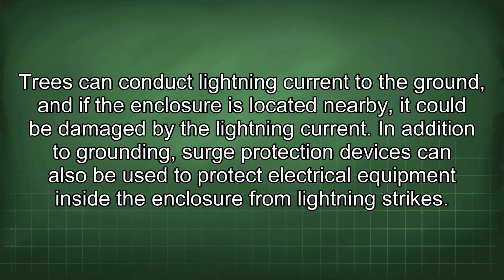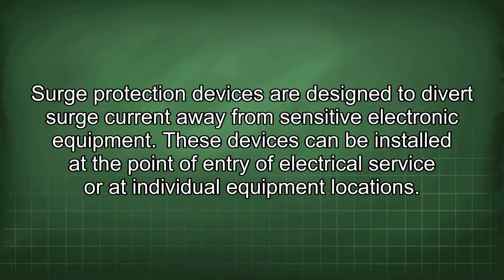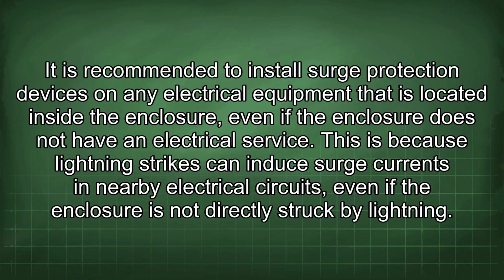the lightning current. In addition to grounding, surge protection devices can also be used to protect electrical equipment inside the enclosure from lightning strikes. Surge protection devices are designed to divert surge current away from sensitive electronic equipment. These devices can be installed at the point of entry of electrical service or at individual equipment locations. It is recommended to install surge protection devices on any electrical equipment that is located inside the enclosure, even if the enclosure does not have an electrical service.